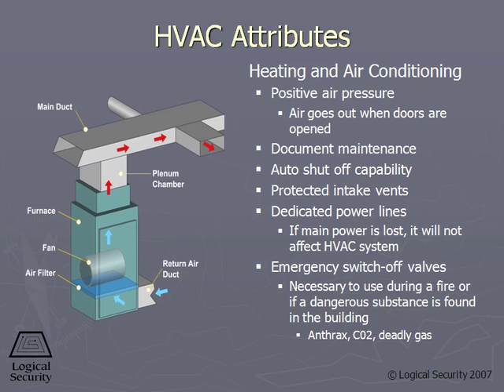One aspect of protecting the physical security of our environment and keeping our facilities habitable is protecting our heating, ventilation, and air conditioning. Some considerations in this regard are that we always want to have positive air pressure into the facility so that the air we're pushing into the facility has been filtered. What this does is make the air flow out of the building. If we have negative air pressure inside the building, in other words, I'm drawing more air out of the building than I'm putting into it, we draw contaminants into the facility, and the facility will soon get polluted with dust and other sorts of debris.